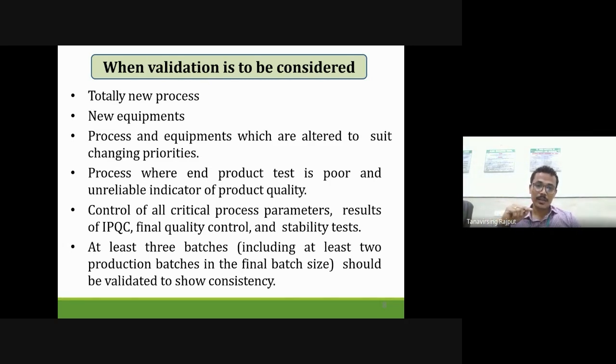Or when the equipment is installed or shifted, or there is any modification or updation in the equipment, we need to validate. Then a process where end product testing is a poor and unreliable indicator of product quality. If the manufacturer did not get a good or appropriate quality product, validation is required.